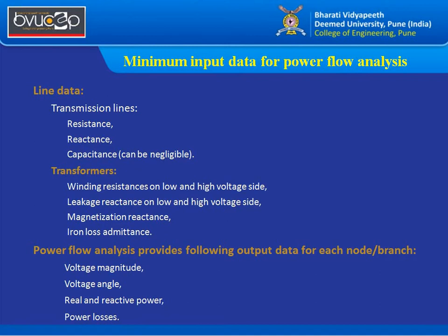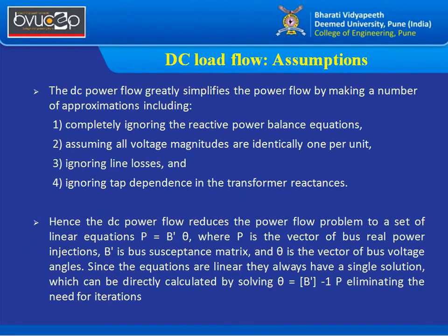For transformers, the required parameters are: winding resistance on LV and HV sides, leakage reactance on LV and HV sides, magnetization reactance, and iron loss admittance. Other transformer parameters such as tap-changing positions, operating temperature, and operating voltage may or may not be required for load flow analysis. The output parameters at each bus include voltage magnitude, voltage angle, real and reactive power, and power losses.